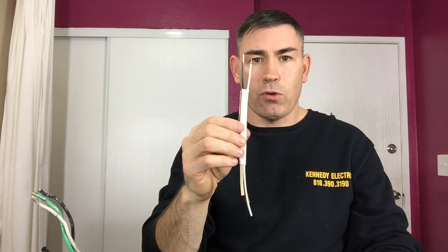A lot of times they want fridges on it. Fridges used to be a dedicated line of 14-2, but not anymore. A lot of inspectors want to see this in 12. Counter plugs are another kitchen circuit. It's got to be in 12-2, and you can jump from one counter plug to the next counter plug, and then the circuit is finished. So you see a lot of this in kitchens, and a lot of the other in living rooms and bedrooms and so forth.